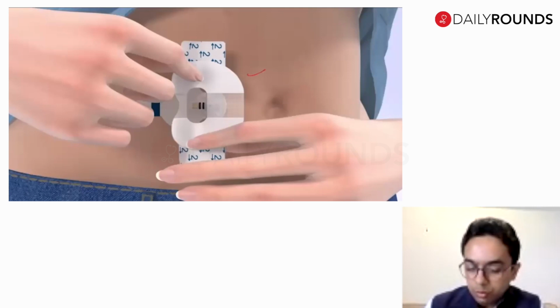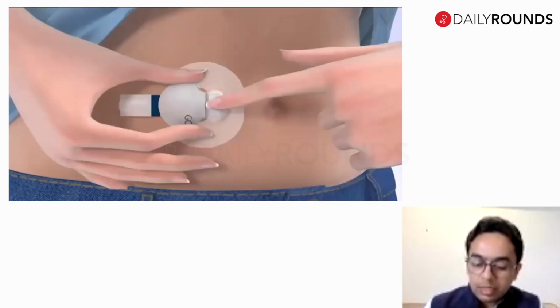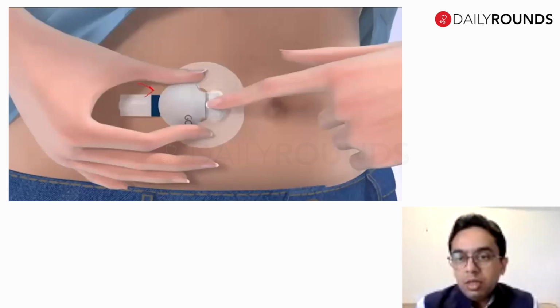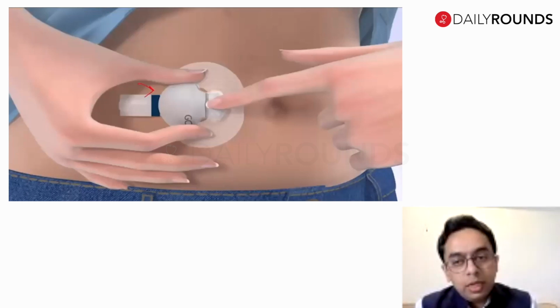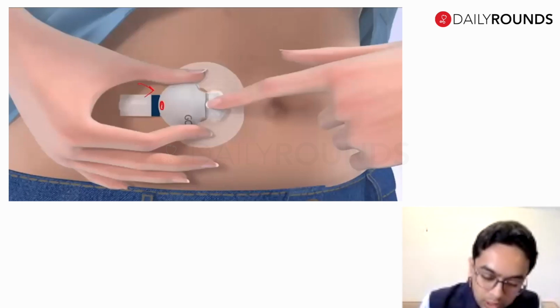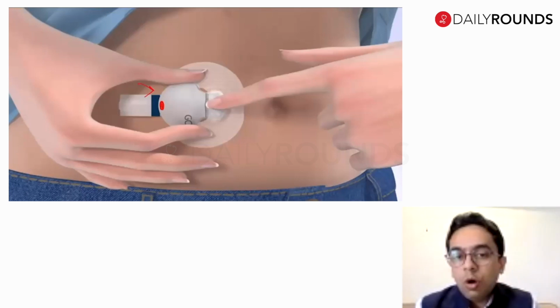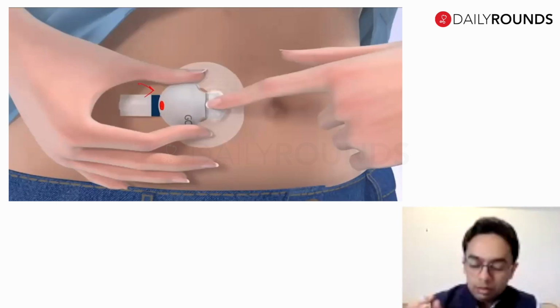Then you remove part two, so it will be attached here. After that, you place your transmitter. You just have to push it. Then again, you will hear a click sound and you will see a green dot here. That means the transmitter is getting information from the sensor and it is ready.